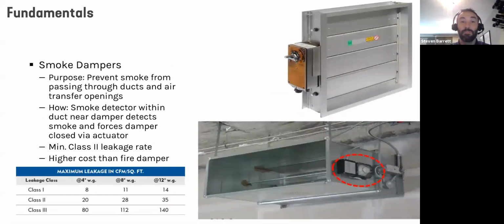Now, moving to smoke dampers, these are a little bit different. They're not quite as simple because they're detecting smoke, not heat. So a simple piece of metal that melts is not going to work. Instead, it requires a smoke detector and an actuator to activate the damper and close it off to stop that smoke from passing through.